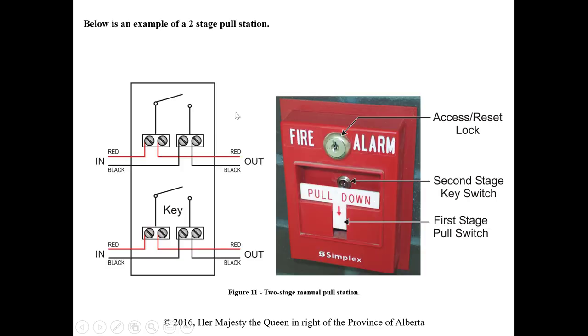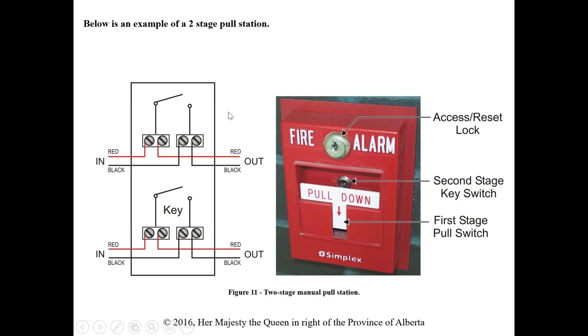There's also a two-stage pull station, which relates to the difference between single-stage and two-stage systems. It has a second key — sometimes behind the panel you pull down. Pulling the station initiates a first-stage alert signal; then you have a maximum of five minutes to get there, determine if there's an actual fire, acknowledge it with the key for the second-stage portion, or initiate a full alarm sequence if a fire is confirmed.